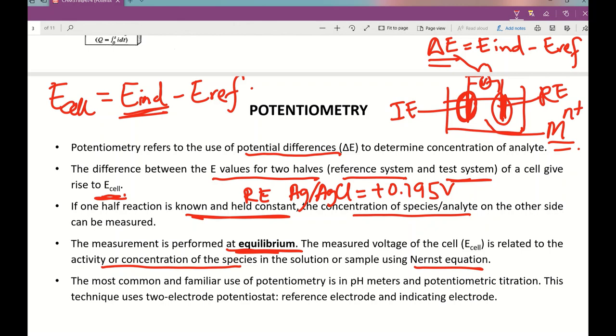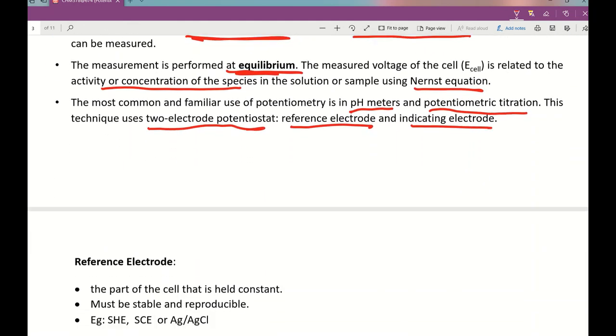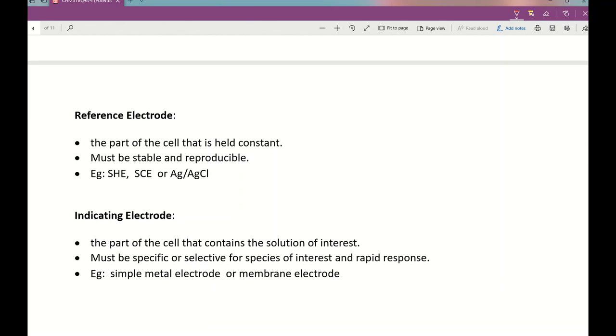The most common and familiar use of potentiometry is in a pH meter, as well as in potentiometric titration. It only uses a two-electrode system consisting of a reference electrode and an indicator (working) electrode. The reference electrode must have a constant, stable, and reproducible value. For example, for SHE the value is zero volts. For SCE, the value is 0.241 V. For silver-silver chloride, as mentioned earlier, 0.195 V.